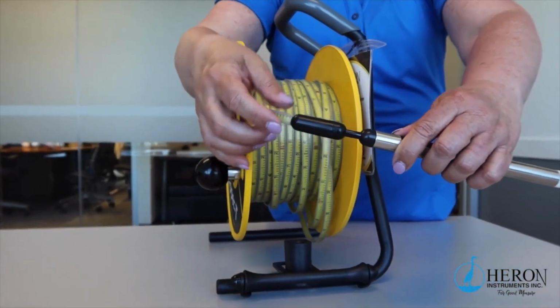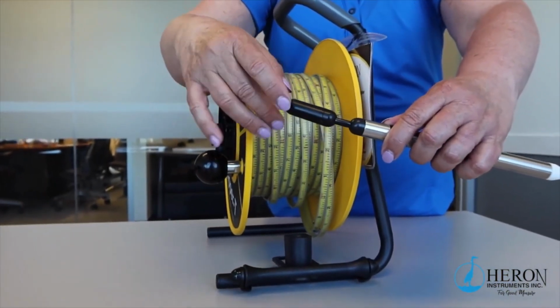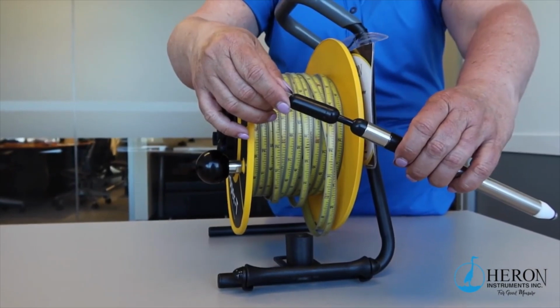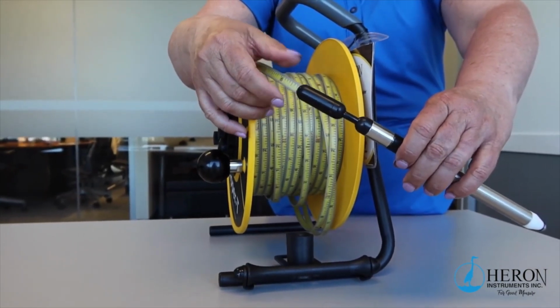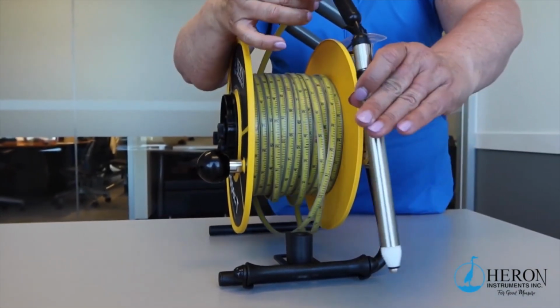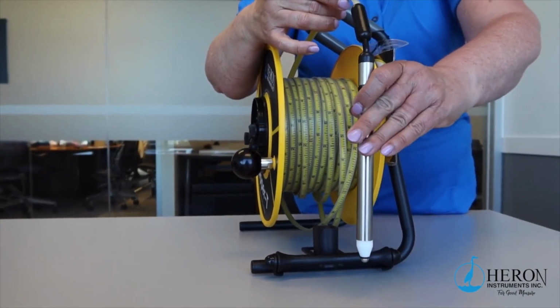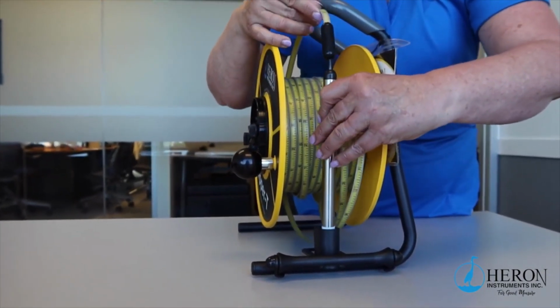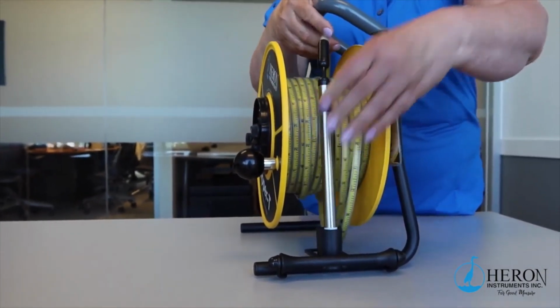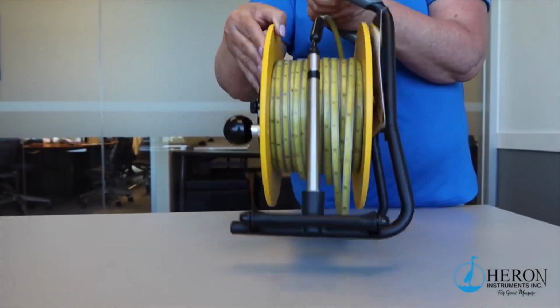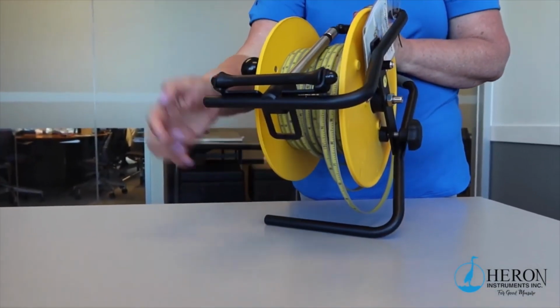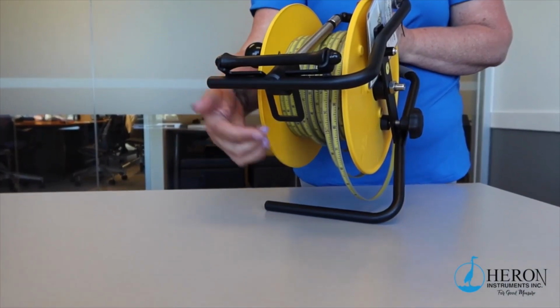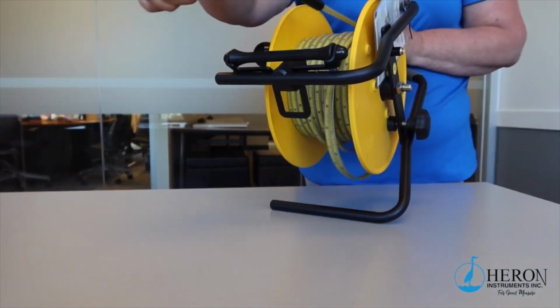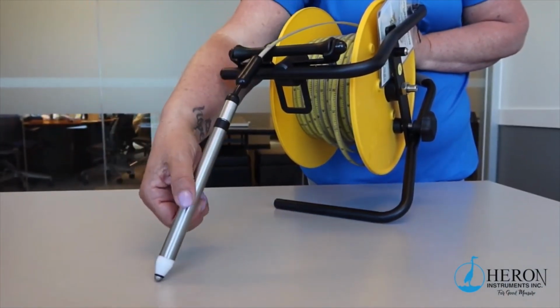There is a shear pin style linkage above the probe, which will break away if your probe gets stuck in the well. Better to save your expensive tape and lose that inexpensive probe, both of which are modular and replaceable as shown in our parts list. The built-in hanger and tape guide is an ideal solution for hanging your unit on the side of the well and for protecting your tape from the sharp well casing edge.